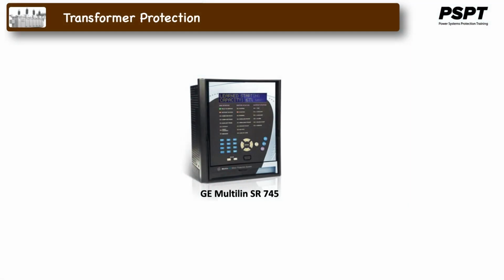The 745 transformer protection system is a full-featured transformer protection relay suitable for applications on small, medium, and large power transformers. The 745 can be applied to 2-winding and 3-winding transformers. Multiple current and voltage inputs are used to provide primary protection, control, and backup protection of transformers, including current differential, restricted ground fault neutral, ground overcurrent, overfluxing, and on-load tap changer compensation. The 745 also includes analog inputs and outputs, while incorporating advanced features such as transformer loss of life monitoring.